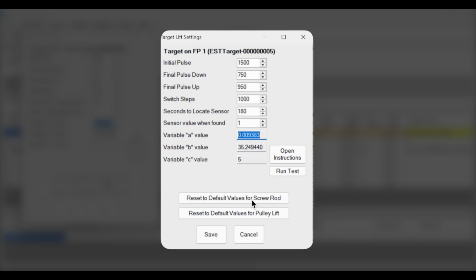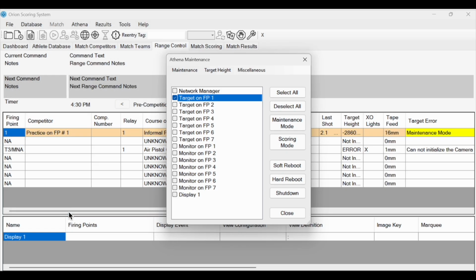Orion will fill in the needed fields based on these measurements. Select Save. Once complete, hop back over to the Athena Maintenance dialog window. Select the same target, if it isn't already selected, then navigate to the Target Height drop-down menu. From here, select Override Range Script, then Kneeling. Once the target stops moving, the aiming bowl should be about 800 mm above the floor.